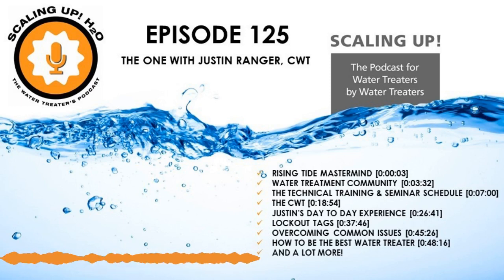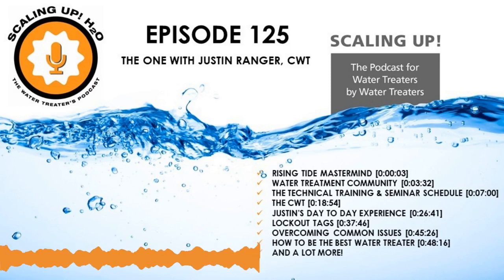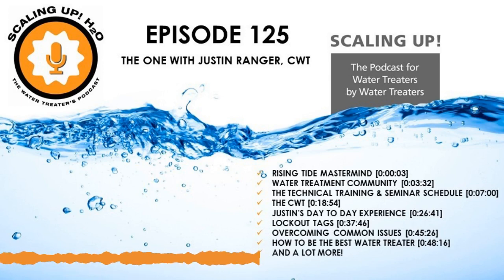One of the plant operators walked in, saw that the feed pump hand-off-auto switch was in the off position, said, 'Oh, that should be on auto,' and flipped it on. Hot DA water started spraying out of the loose pipe fitting. Fortunately nobody got hurt and nothing was damaged, but that situation really opened my eyes to the real potential for people to be injured.